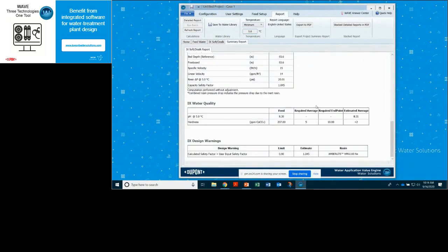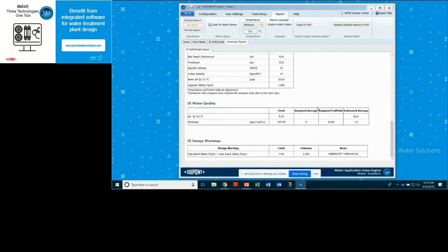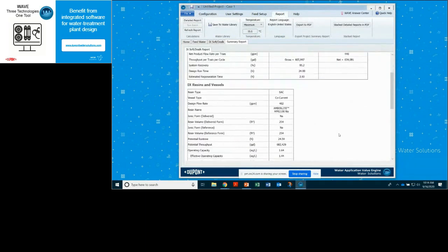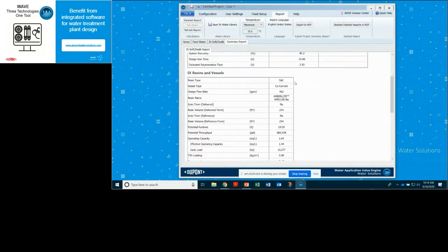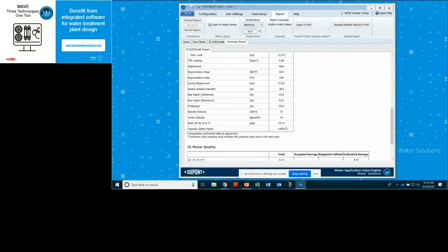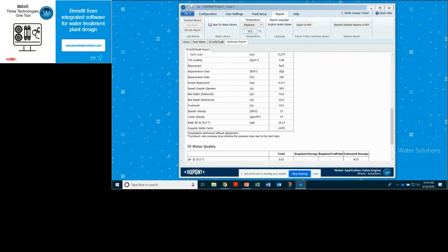So something that I do in this scenario, or I've done, so one is, this is a nice feature if you have a design in a pretty broad temperature range to quickly evaluate the conditions at the different temperatures. So we could also go to the maximum now if we are curious about the max, but this also gives you a glimpse at projected throughput for a given temperature within a set design that you've just set. Yep. But one thing I'll note is when you do make that change up there, if you go back and make changes in Wave, it will refresh the design at the temperature that you set up there. So Garth, if you don't mind setting us back to the design temperature.